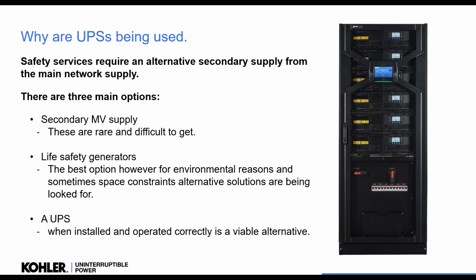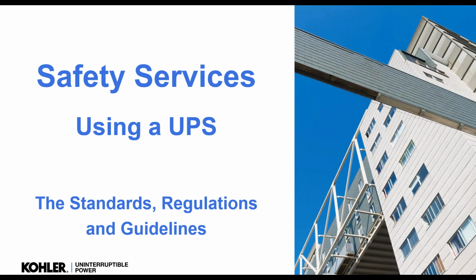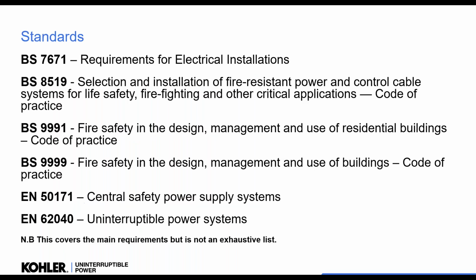So that is very important, that it has to be installed and operated correctly. Okay, and we've seen a lot of systems not being done that way, and hopefully this sort of guidance and the education and the working with guidelines and standards, we're trying to change that and make sure it's addressed and we fit a nice safe system. So the different standards and regulations we have, of course, we've got BS 7671, we have 8519, which is for selection, installation of fire resistance power control cables and systems for life safety.